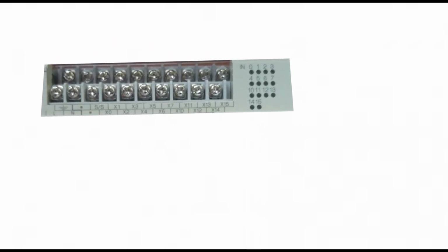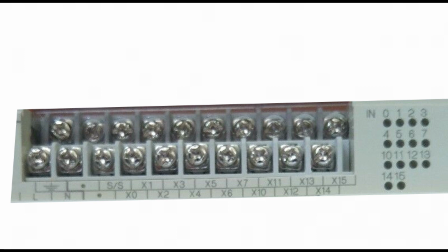On the top side of the PLC, it will look like this. Hot goes on to the L terminal, and neutral to the N terminal, and ground goes to this terminal. The S/S terminal needs to be connected to 0 voltage DC. The rest of the terminals are where you will connect inputs with 24 voltage DC.